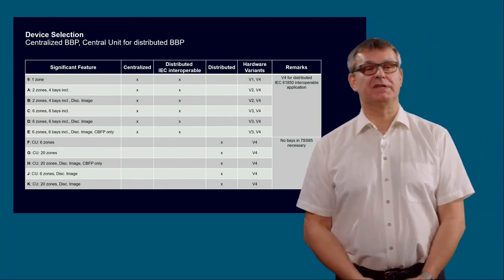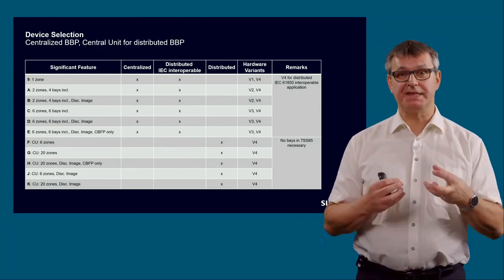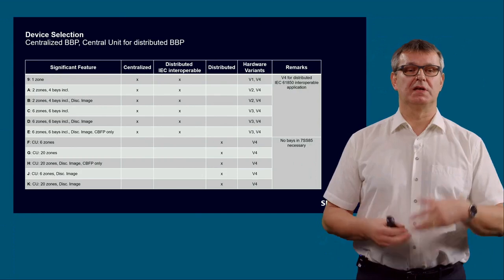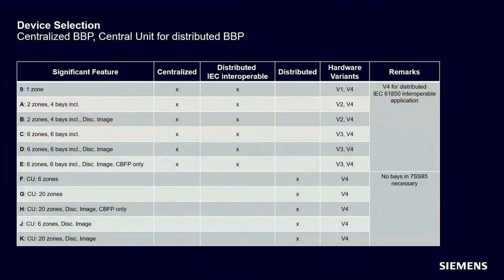And last but not least, we have the significant feature for the fully distributed solution for the 7SS85CU. These are the significant feature F, which is for only 6 zones. Once again, no disconnector image available. And okay, G, the CU for up to 20 zones. Not very common, this issue. Very seldom to have really 20 zones without a double bus bar or triple bus bar. We have once again H, the CU for 20 zones, disconnector, and circuit breaker failure protection only. That's the same as I have explained with the significant feature E for the centralized bus bar protection.